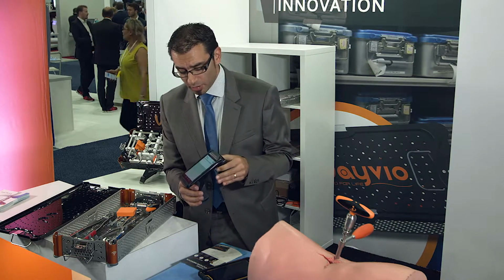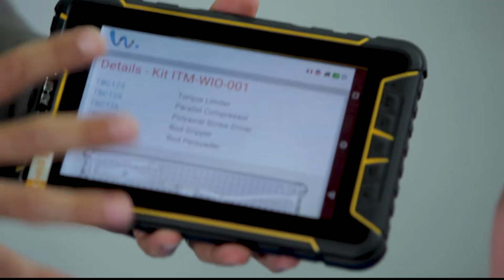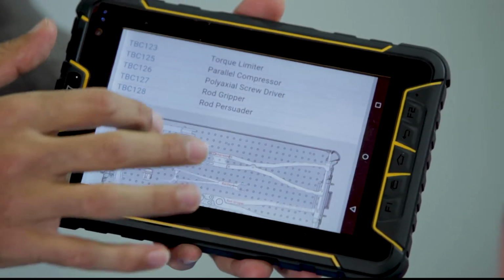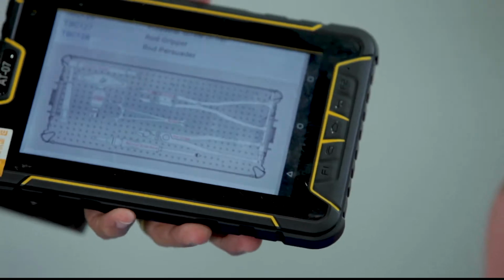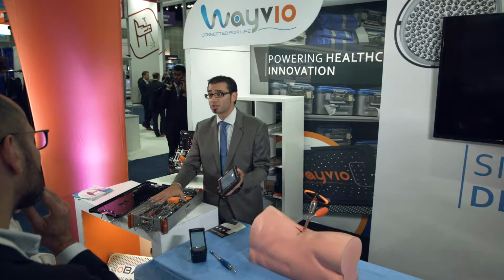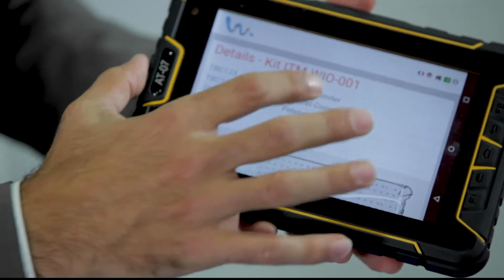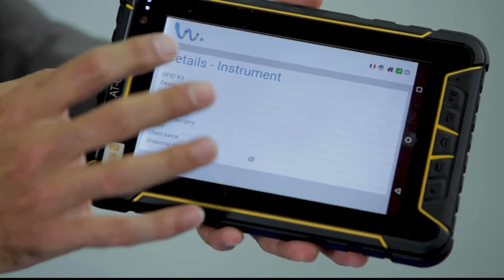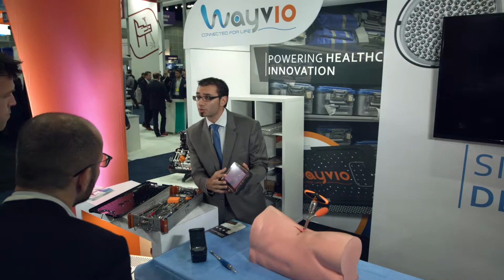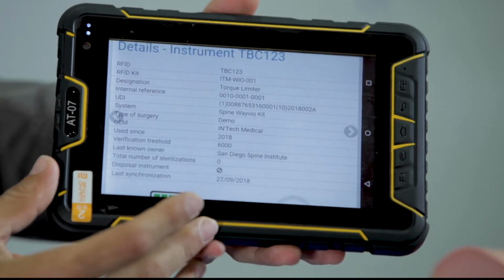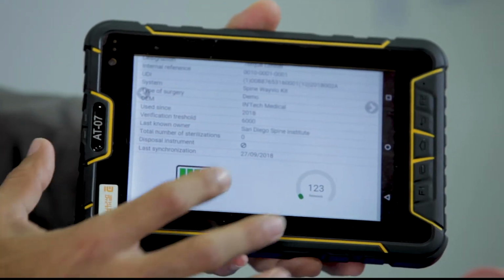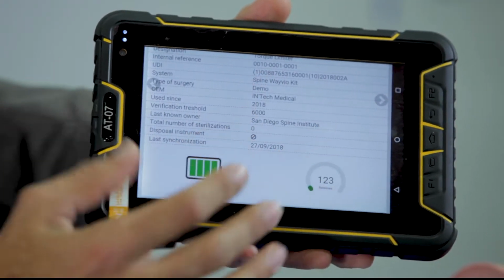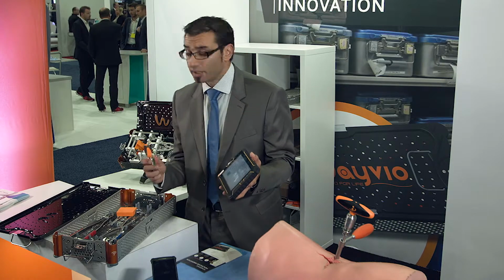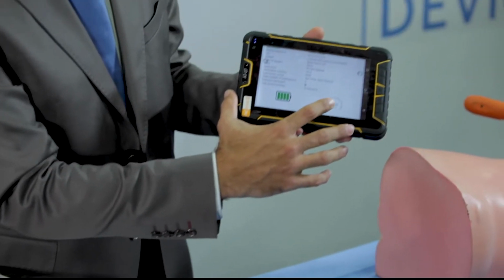If you push the detail button, you have all the instruments inside. Here is how it looks on a bigger tablet. You have the whole list of instruments inside. You also have a layout picture to help you recompose the tray instead of relying on what's etched inside the box. And if you look at one instrument precisely, you will have a lot of data from UDI to internal references, when the instrument was first put on the field, what was the last synchronization date, the number of times it's been sterilized, and for the torque limiter, how many times it's actually been released.